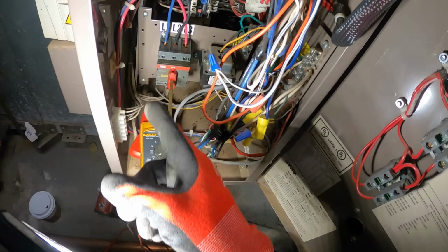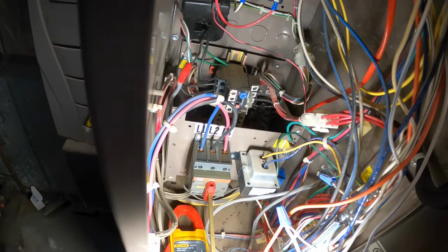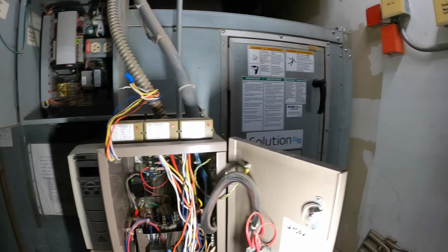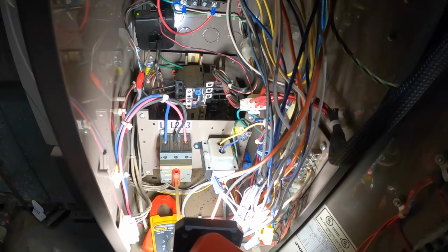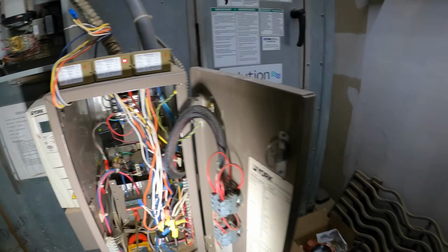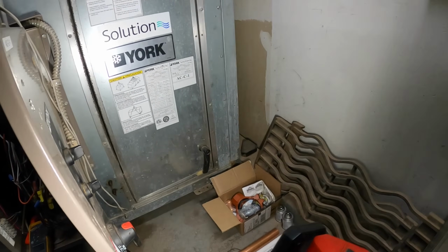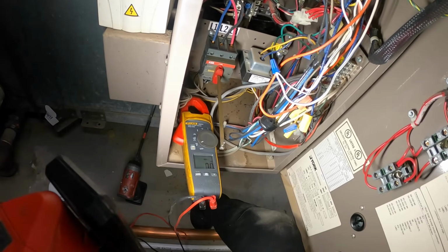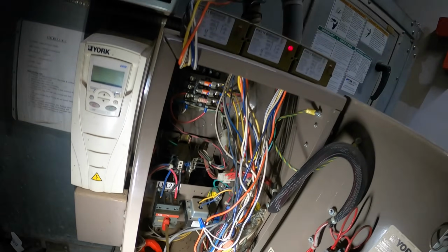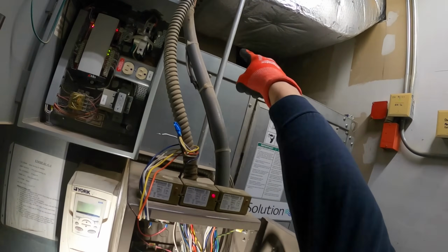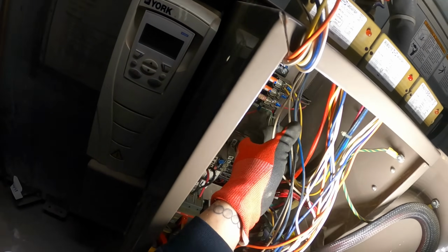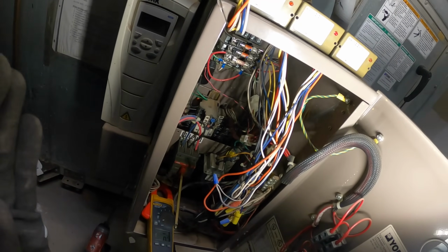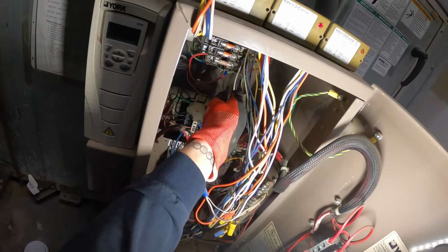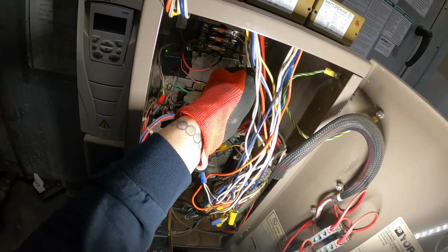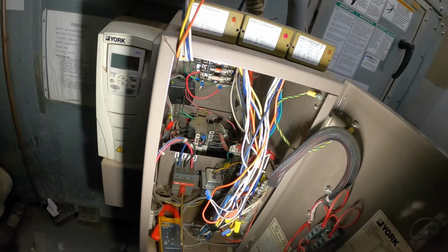I'm gonna have to take off this plate and pull it out to get back in there. What a horrible design. You got all the space in this world, this giant unit. You can't give us proper access to the motor starter, the main component here. That's our starting component for this unit. And then if you see this conduit, it's these wires here. The hell was that? Something's loose in here. Hold up.